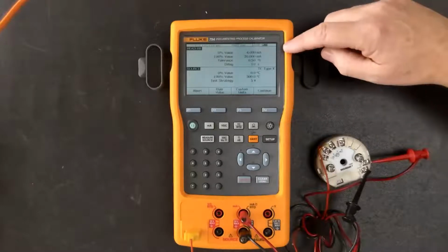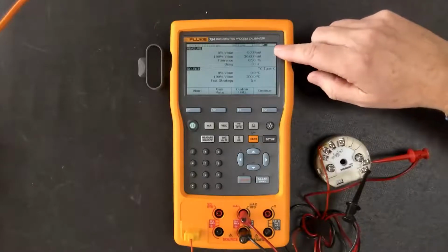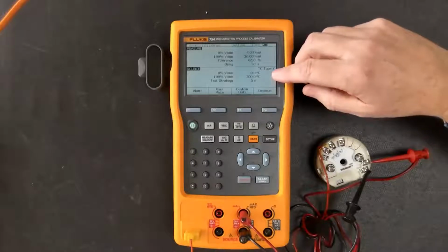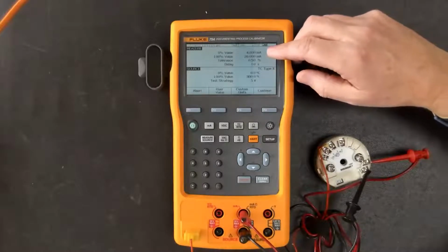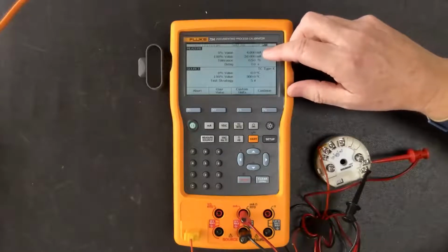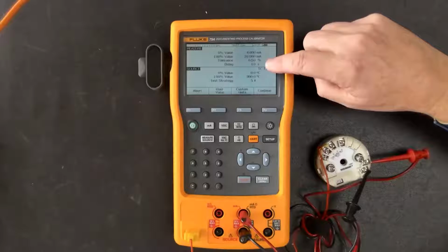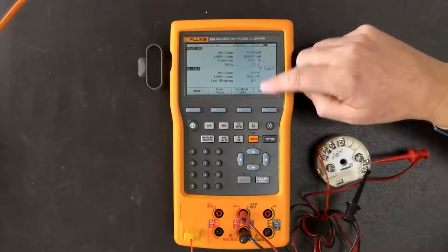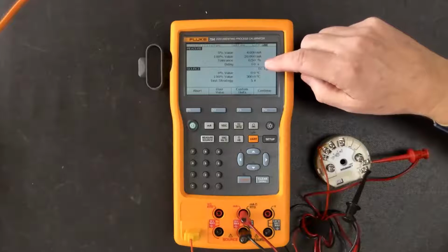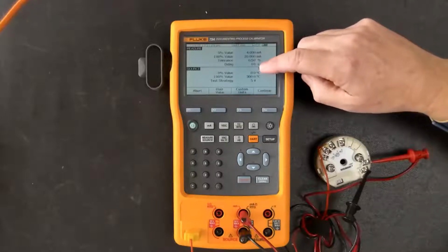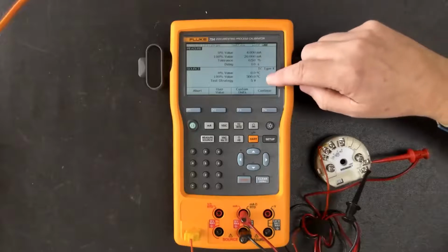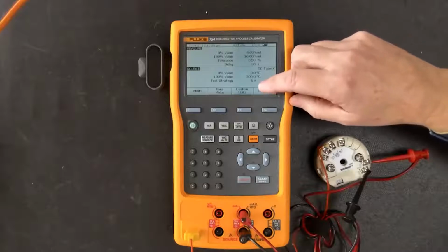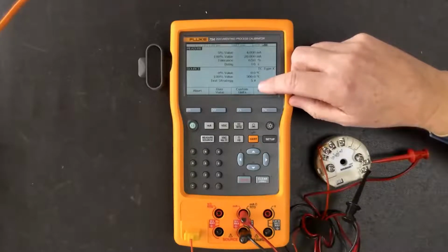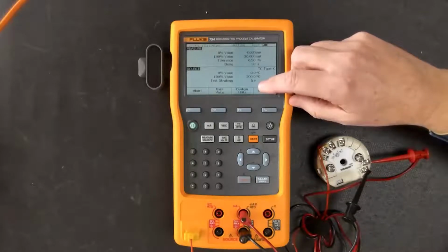And you'll notice all the information that I need to know about my calibration has been downloaded from ProCal to the calibrator. So we know that our measure is going to be 4-20 milliamps. The tolerance has been set in this case to 0.5. All of this is selectable by the user or the admin. We're setting up a 10-second delay because we're going to do an automatic calibration. And then the source is 0 to 300 degrees C. And the test strategy is how many test points are required for the test. And again, this is determined when you're setting up the configuration in ProCal.